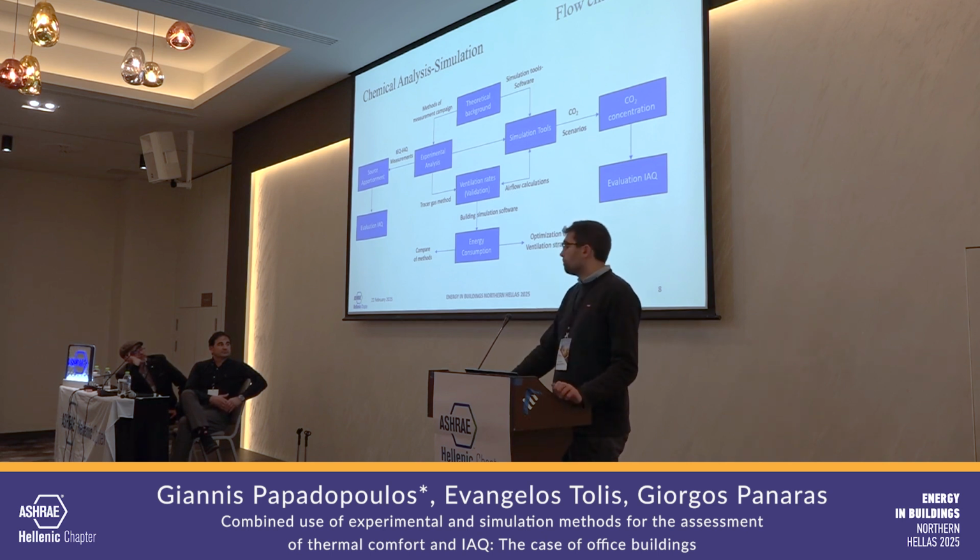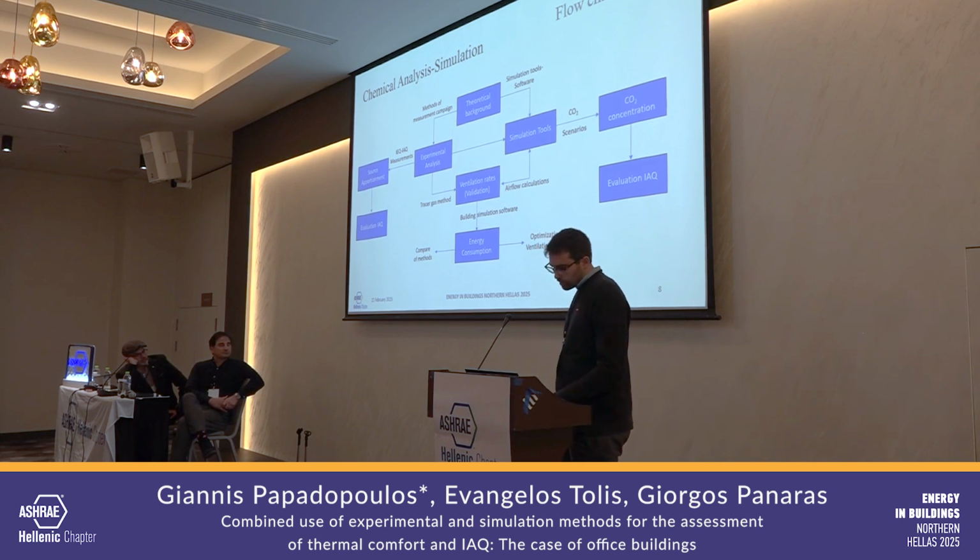So if we calculate the ventilation rates, we go to the energy consumption according to the ventilation rate and can compare these different methods. And one more thing is that using a simulation tool, we can make different CO2 scenarios and ventilation scenarios to see how these change the indoor air quality of our offices.